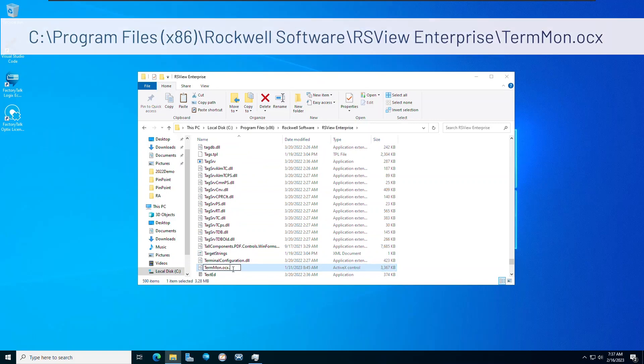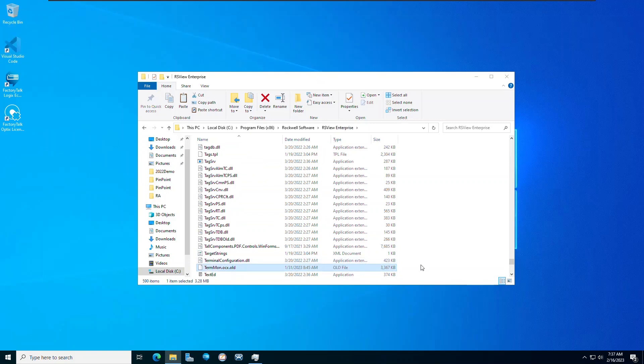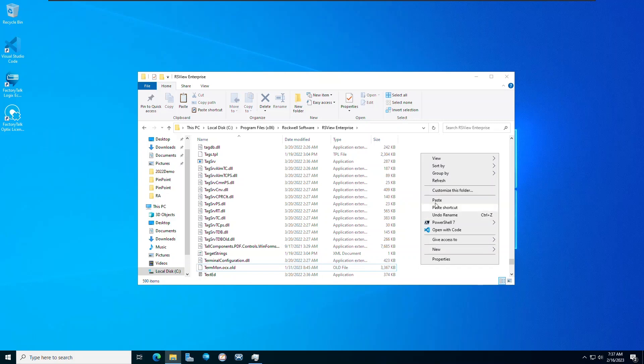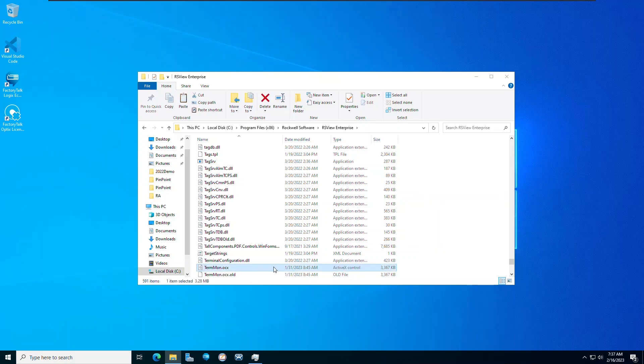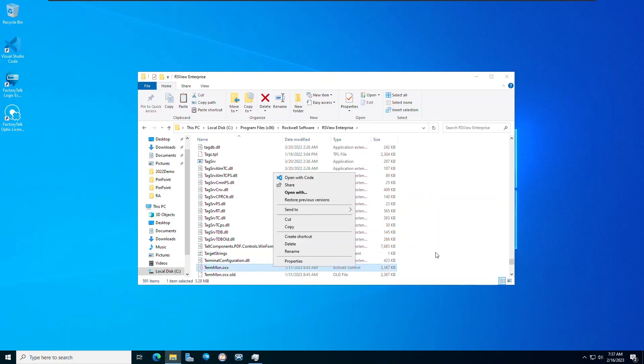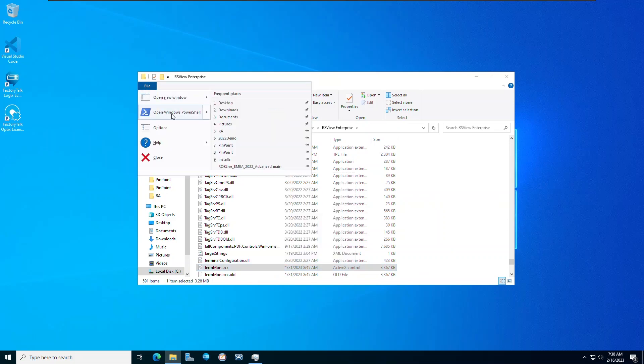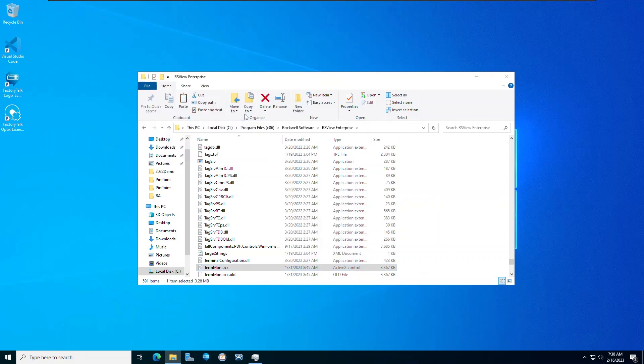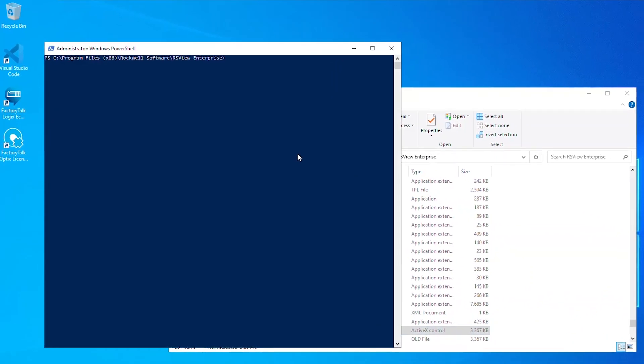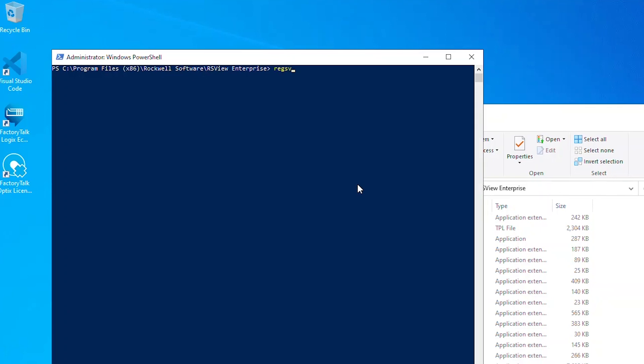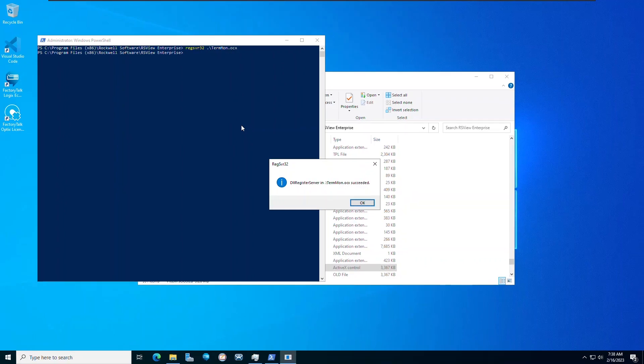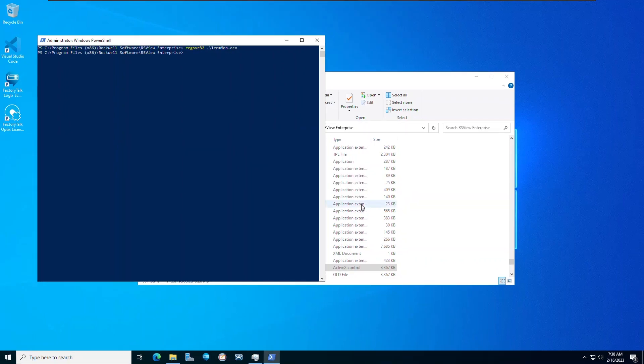Rename the old file and paste in the new TermMon.ocx file. Next, navigate to Open Windows PowerShell as Administrator to point to the appropriate ActiveX control location on the computer's drive. Input the command REGSVR32 followed by the TermMon.ocx file path and press Enter. You will see the action has succeeded and your ActiveX control is now registered.